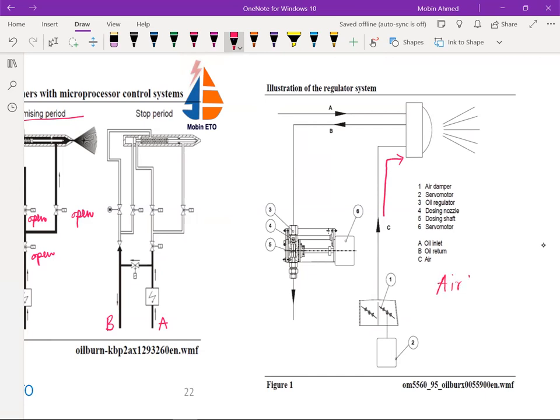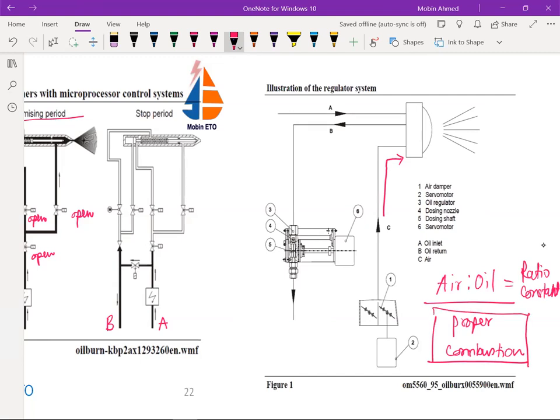So the air and oil ratio has to be always maintained. This ratio should be constant always. This ratio has to be constant for proper combustion. Otherwise, there is going to be black smoke or white smoke. The smoke or exhaust should be colorless. Exhaust should be colorless when it is running. Not during starting. During starting, it is always a black exhaust. But once the firing has started and your boiler is in operation, it should be a colorless exhaust. So that's why these servo motors are there. They always have to keep one ratio of both.